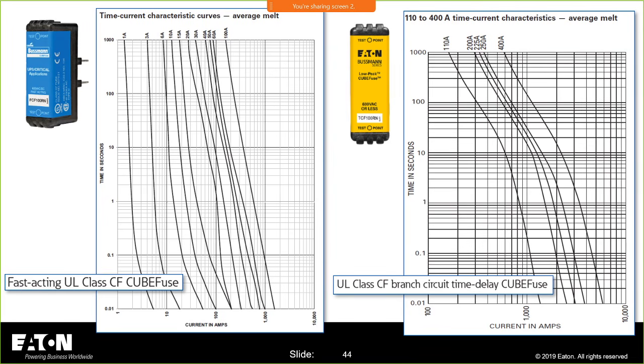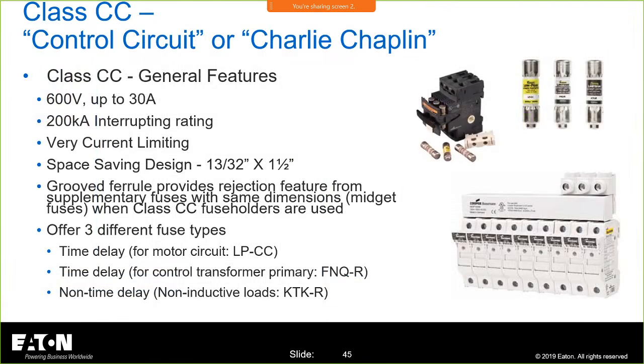There's both in the cube fuse world. One is fast acting. One is a time delay fuse. And then you got your Charlie Chaplins or your control circuits because of that little hat, right? And where do we see these? We see these on your control power transformers, etc. They have that groove ferrule. Again, that's a rejection feature. Very current limiting devices up to 200,000 amp interrupting rating. They're up to 30 amps. They don't go any higher than 30 amps.